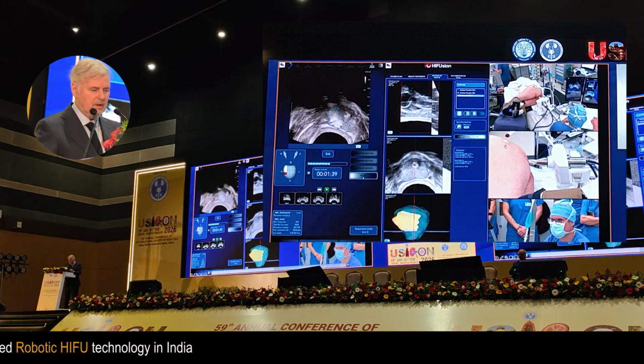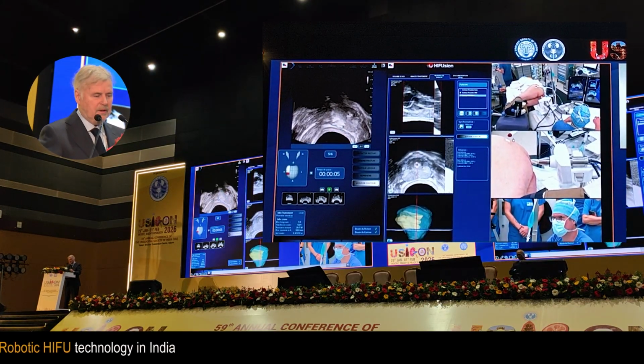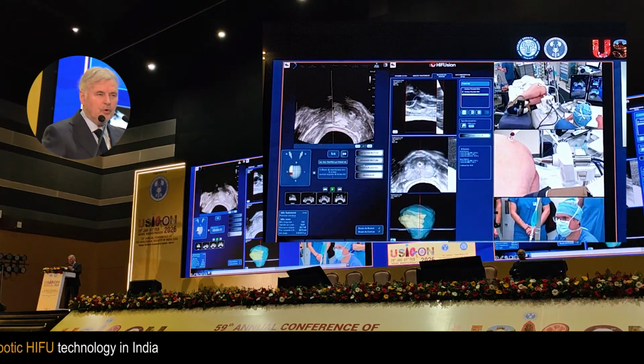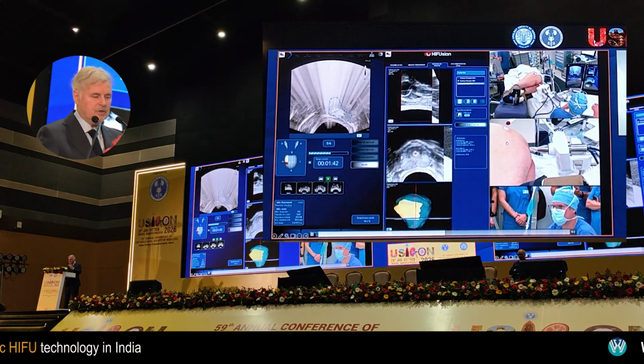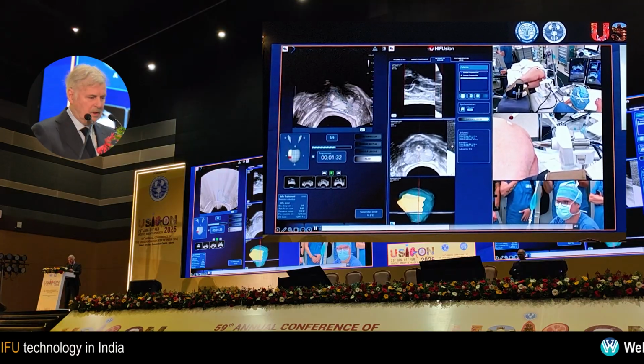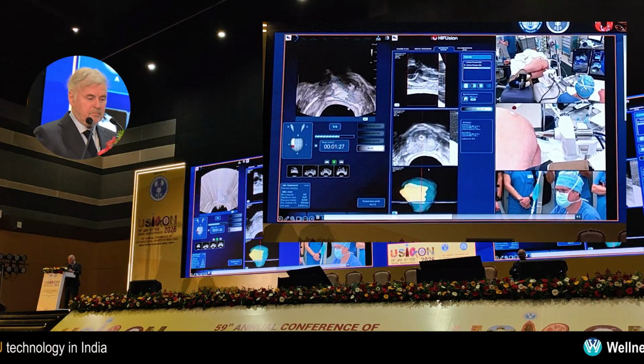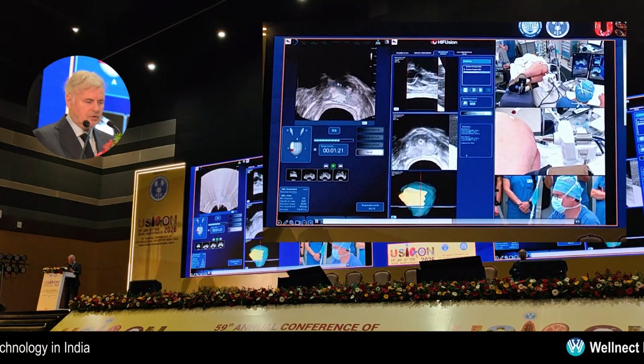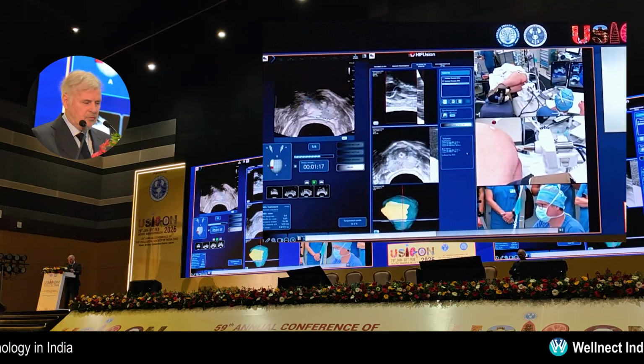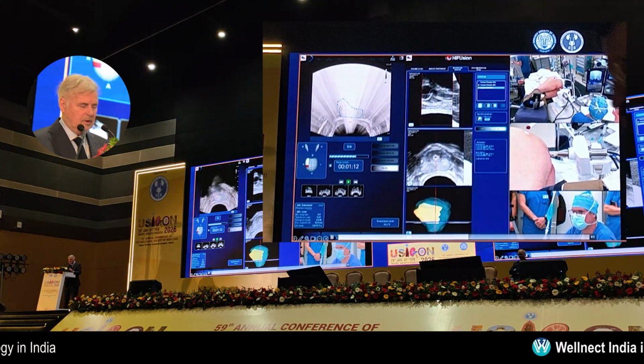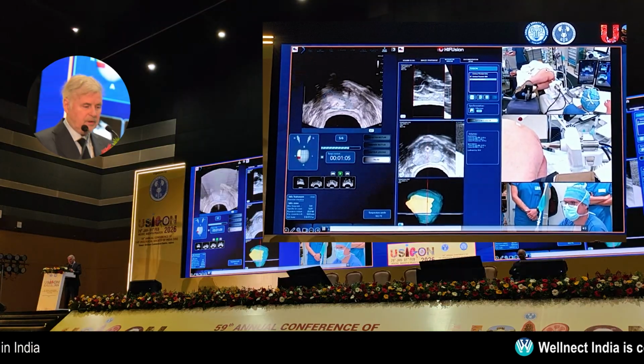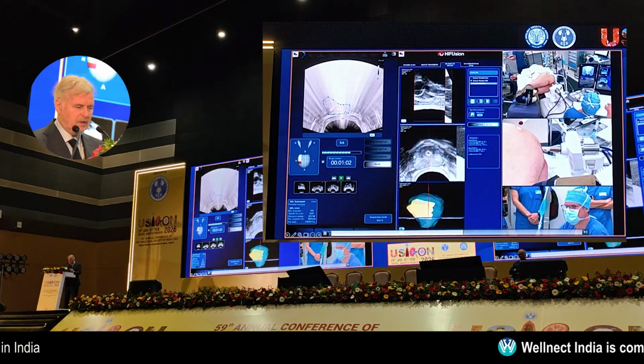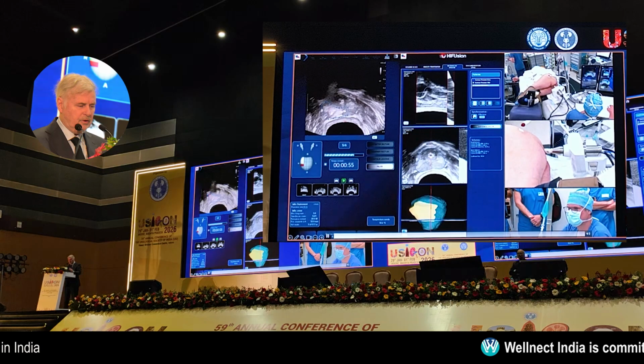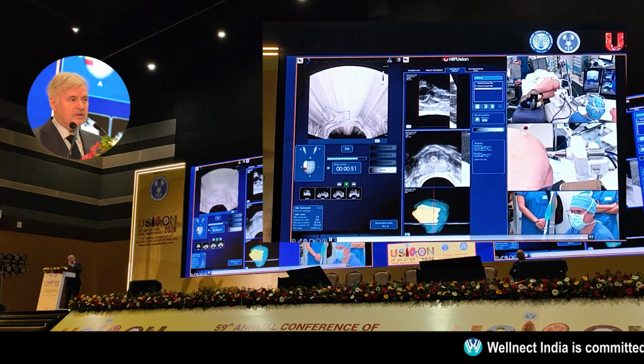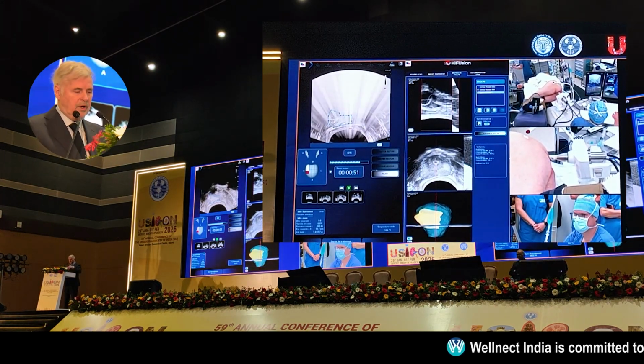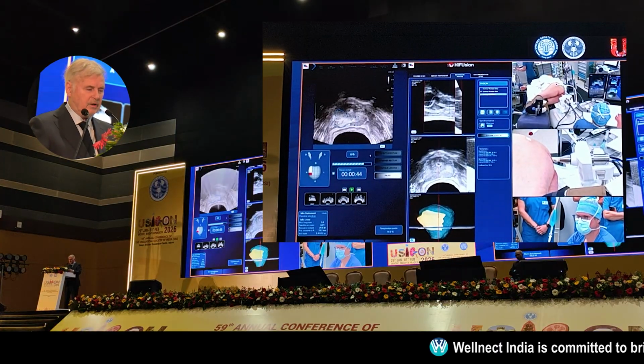As you can see here, we have a step that if the patient moves even 2 millimeters, the machine will stop automatically. So this part of the treatment is totally robotized. We just have to look after the cavitation, for example, that appears here, the limits of the prostate. It should not be blurred, and if so, it's very easy to stop the treatment, wait for a few minutes, and start again.